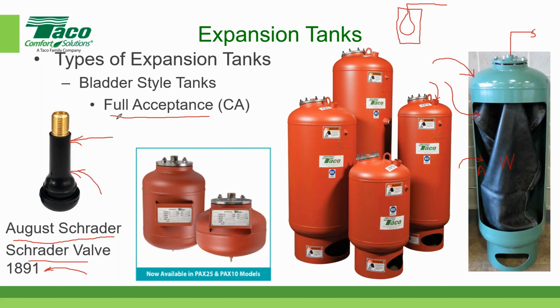Okay, so the term full acceptance means that the bladder itself has the same physical volume, or holds the same amount of volume, as the steel container. So if the steel container - just making up a number here - is 200 gallons, then the bladder can also hold 200 gallons; it can accept an expansion volume of 200 gallons. So when the balloon or bladder has the same volume as the steel container, we say that's a full acceptance tank, and that's where the definition comes from. So the full name is a bladder style full acceptance tank.